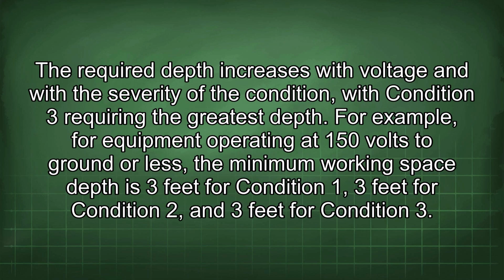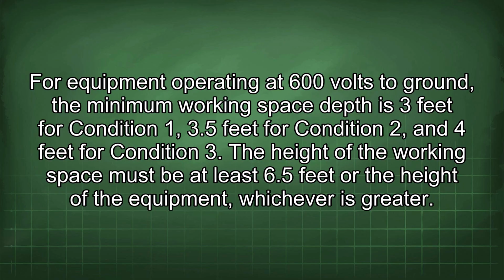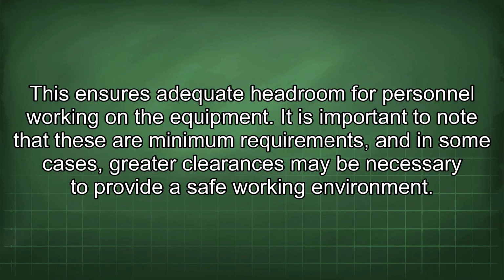The required depth increases with voltage and with the severity of the condition, with Condition 3 requiring the greatest depth. For example, for equipment operating at 150 volts to ground or less, the minimum working space depth is 3 feet for Condition 1, 3 feet for Condition 2, and 3 feet for Condition 3. For equipment operating at 600 volts to ground, the minimum working space depth is 3 feet for Condition 1, 3.5 feet for Condition 2, and 4 feet for Condition 3. The height of the working space must be at least 6.5 feet or the height of the equipment, whichever is greater. This ensures adequate headroom for personnel working on the equipment.